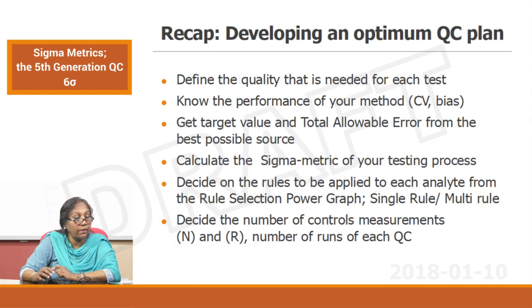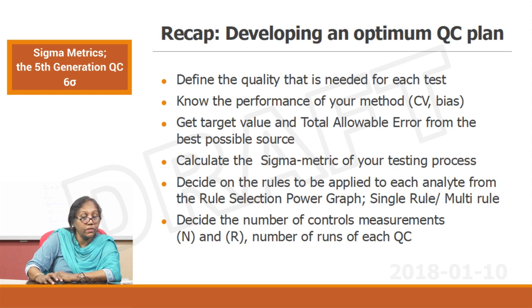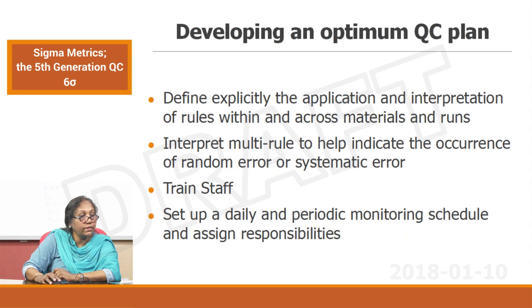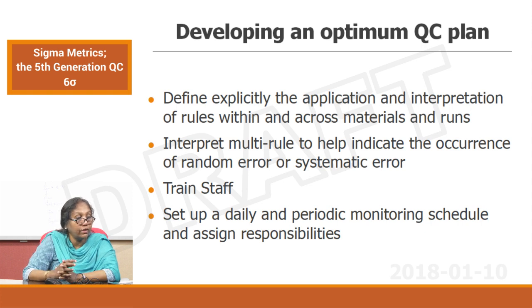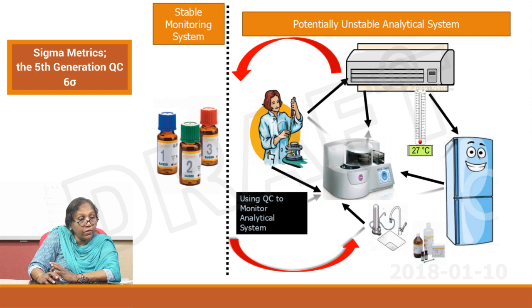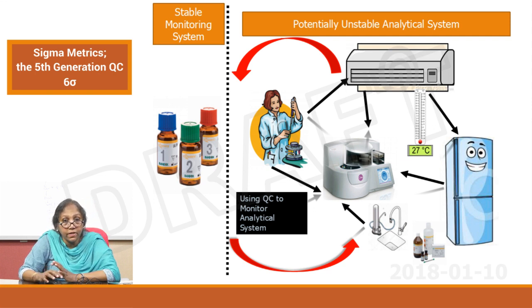Statistical measures include using multi-rules, looking back to previous runs, and increasing the number of QCs and runs of QCs. Non-statistical methods include deploying staff with special training for low sigma tests and increasing supervision. Developing an optimum QC plan: define the quality needed for each test, know the performance — CV and bias — get target values, get TEA from the best possible source, calculate the sigma metric, decide on the rules to be applied on each analyte from the power function graph — whether single or multi-rule — decide the number of control measurements, train your staff, and set up daily and periodic monitoring schedules with assigned responsibilities. To conclude, a stable monitoring system using internal quality control will safeguard a potentially unstable analytical system if you understand and implement all these things adequately. Thank you.